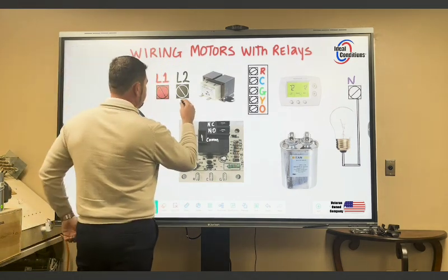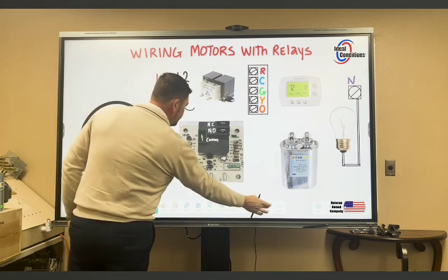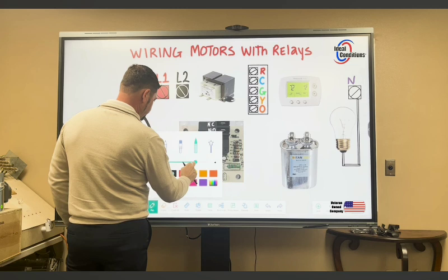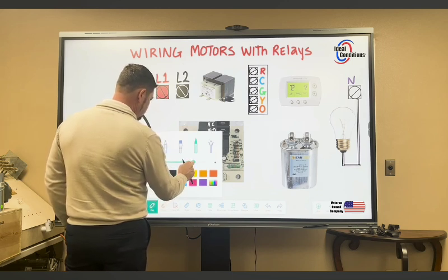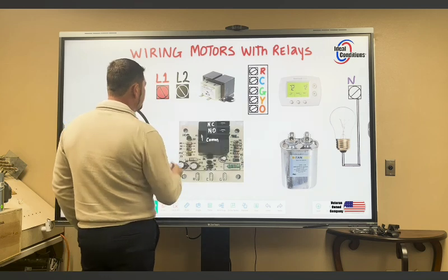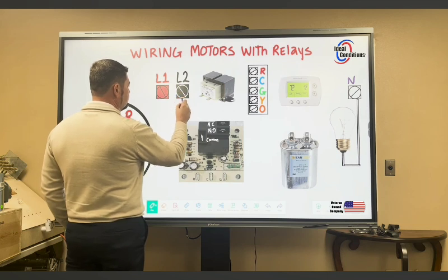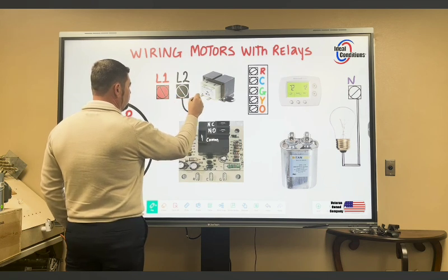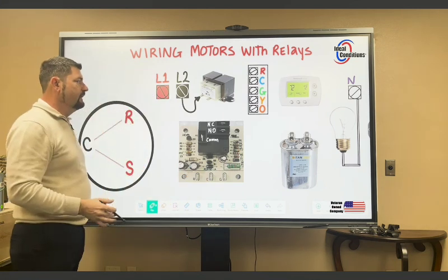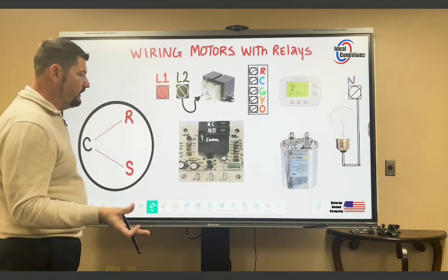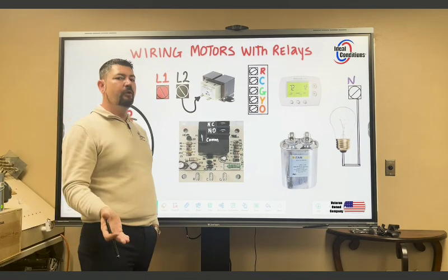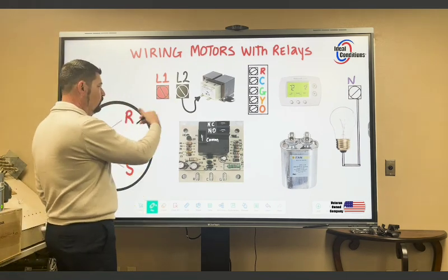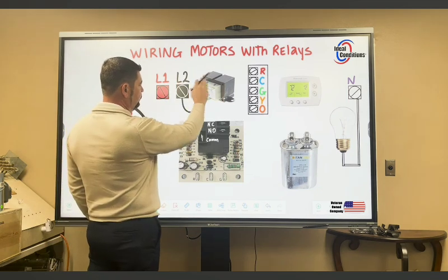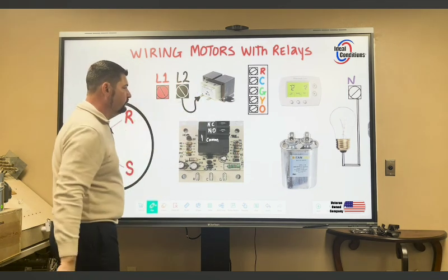We're going to go ahead and take L2 and get my marker size just right here. Okay, we're going to take L2 and we're going to land everything that L2 needs to be on, and then when we're done with L2, we'll step back and inspect it, verify that everything looks good. Once it looks good, then we'll go to L1. Now, I don't have to do it in that order just because L2 is the closest thing to my transformer. I'm just starting off with L2.